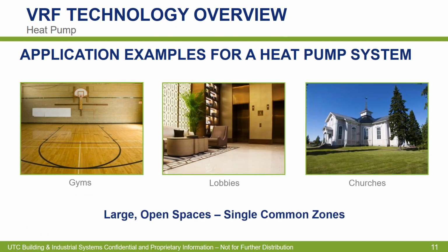So good applications for heat pump systems: gyms, lobbies, churches. So let's think about it, large open spaces, single common zones, right? So you're going to either have a request for cooling or a request for heating in these large spaces, which is a good fit for heat pump, because there's no conflicting demands, right, from what the occupant needs, whether it be cooling or heating.